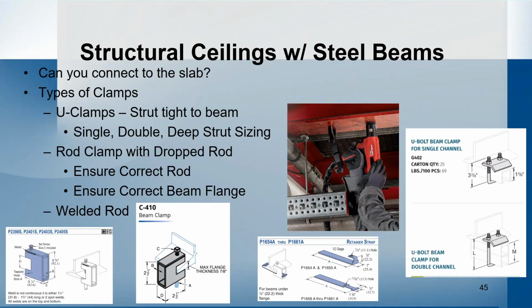So for a new type building where you have steel beams, one thing you need to check is if you can connect to the slab. On some projects you're not permitted to connect to the slab, so you have to go directly to steel. There's a number of different ways to do that. A common way is the U-type clamp. So you have strut tight to the beam, and that can be single, double, or a deep strut. And you need to size your U-clamp specifically for that.